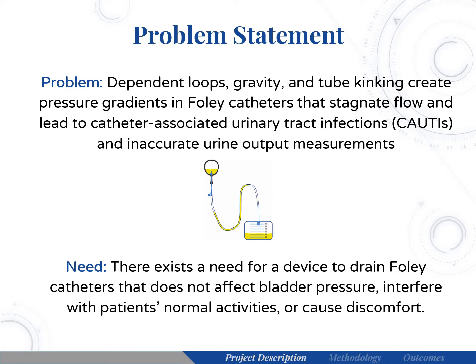The current Foley catheter design is prone to non-homogeneous pressure gradients as a result of dependent loop formation, airlocks, and tube kinking. These irregular pressure gradients can stagnate urine within the line, decreasing urine output measurement accuracy and increasing the likelihood of CAUTIs. Currently, infections are avoided with hourly nurse interactions to manually propagate stagnant fluids in a procedure colloquially known as a Foley salute.